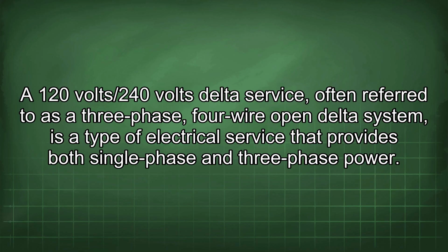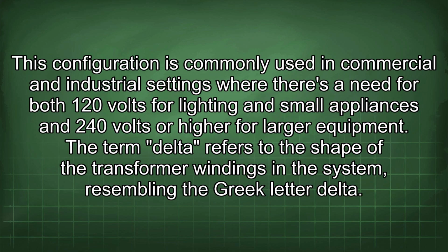A 120V/240 volts delta service, often referred to as a three-phase, four-wire open delta system, is a type of electrical service that provides both single-phase and three-phase power. This configuration is commonly used in commercial and industrial settings where there's a need for both 120 volts for lighting and small appliances and 240 volts or higher for larger equipment. The term delta refers to the shape of the transformer windings in the system, resembling the Greek letter delta.